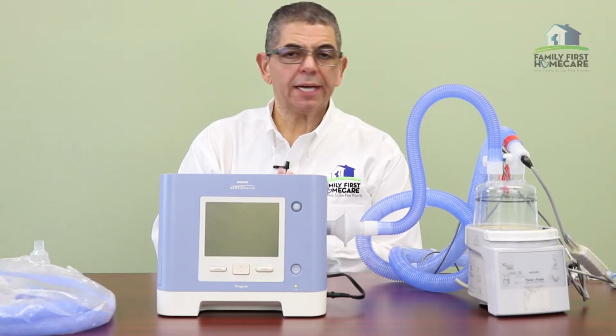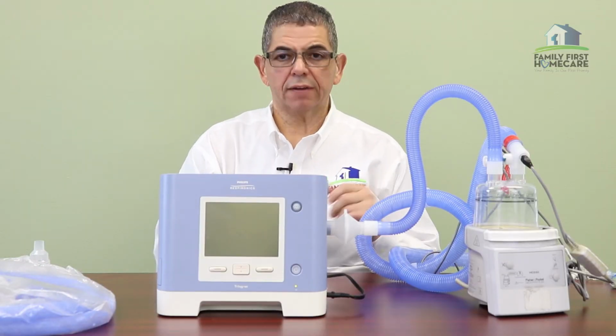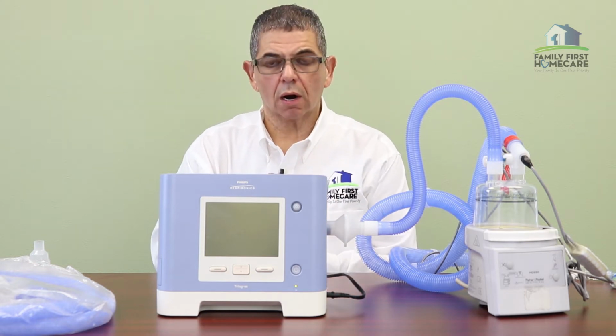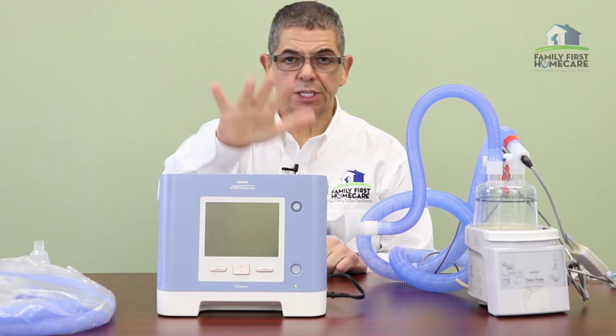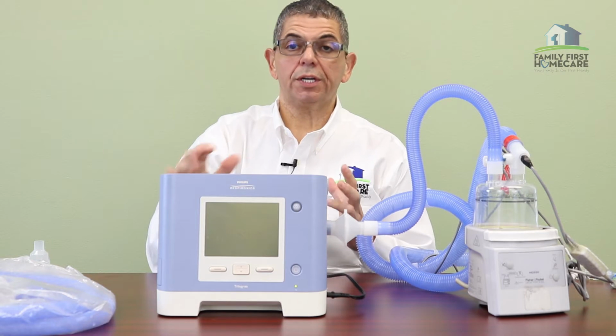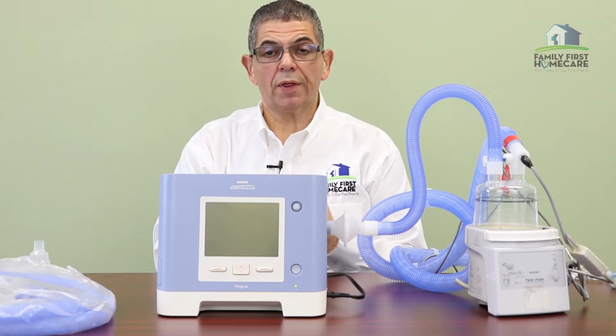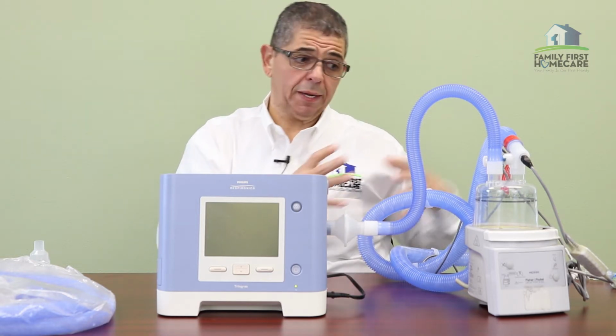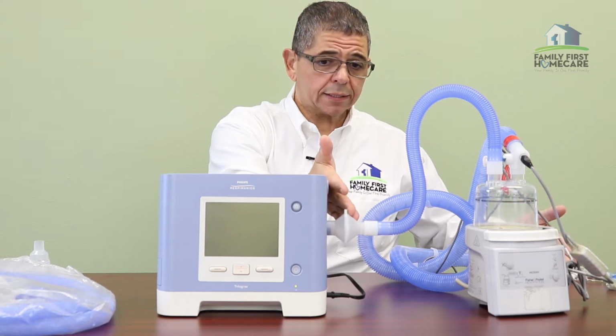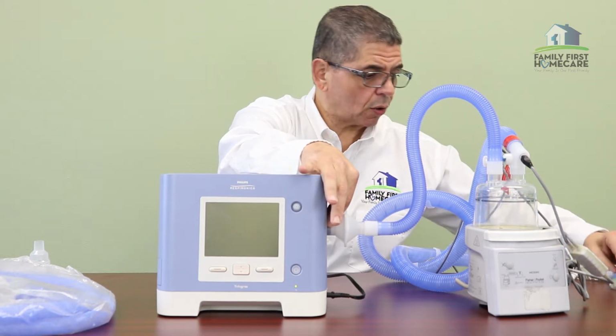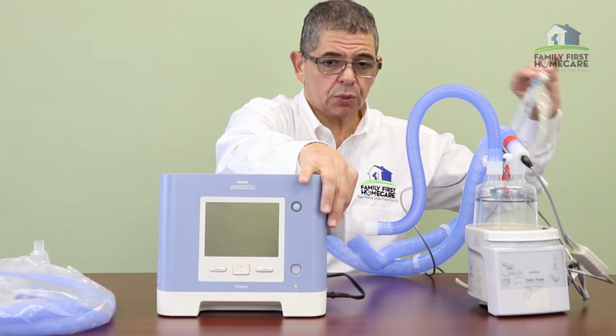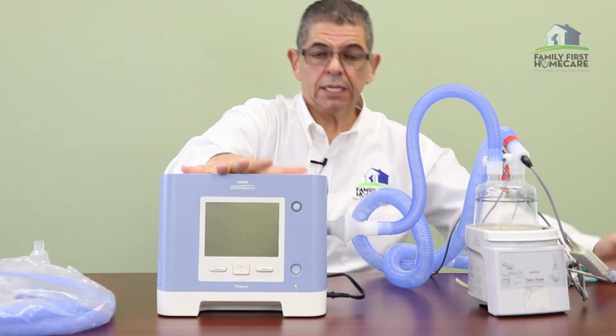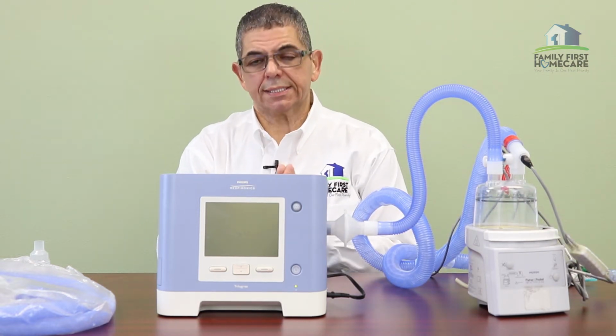So now your patient is on the machine, everything's fine, and all of a sudden it starts to alarm. We're not going to simply shut the alarm off. We know that there's a problem. We know that it's going to be in one of three places. It's either going to be in the patient, in the circuit, which is everything from the bacteria filter all the way to where it connects to the trach, or in the machine itself. So our priority always is the patient.